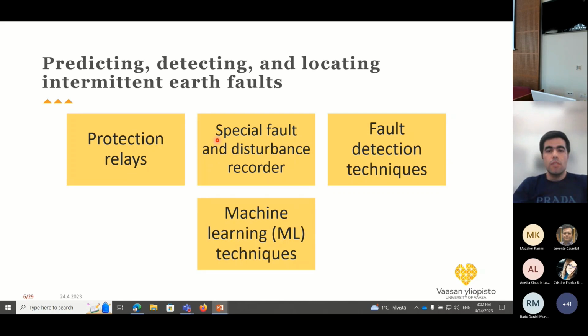Another idea is using a special fault and disturbance recorder, but they need a higher sampling rate, which in turn results in a higher cost, and it's not cost effective to use such methods, especially in MV or LV systems. The next one is using other methods such as traveling waves. Again, they are not cost effective, and they are just used in high voltage, maybe for 400 kilovolt, and there are some relays for this purpose. And the last one, which becomes handy in this situation, is machine learning techniques.